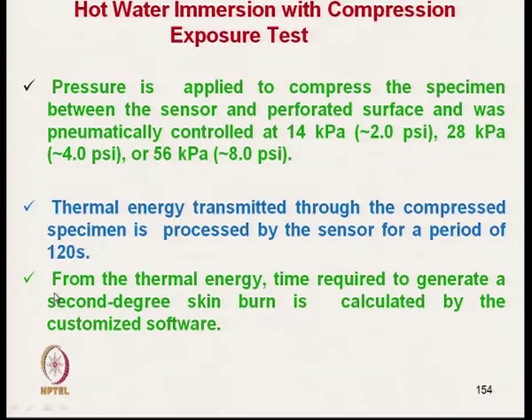The thermal energy transmitted through the compressed specimen is processed by the sensor for a standard period of 120 seconds. From the thermal energy data, the time required to generate a second degree skin burn is calculated using customized software, allowing prediction of the second degree burn.